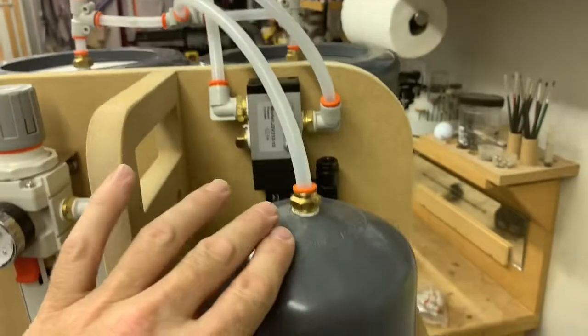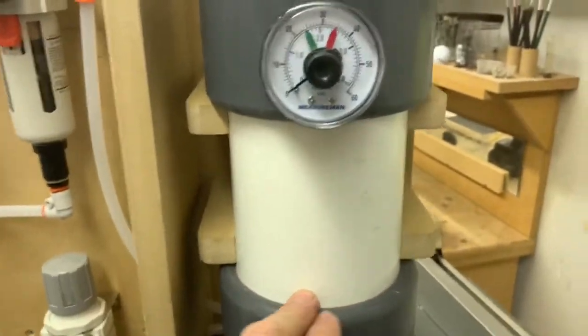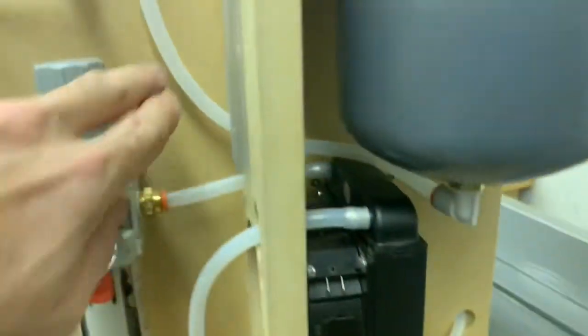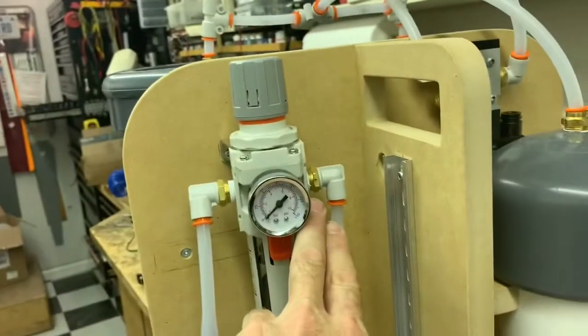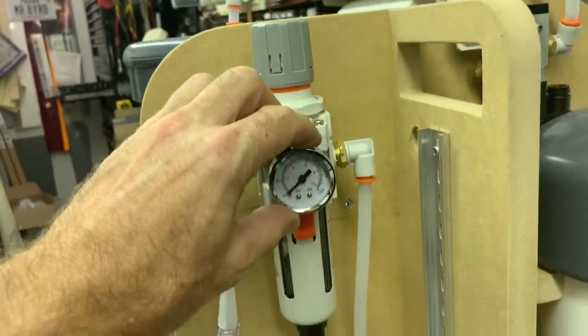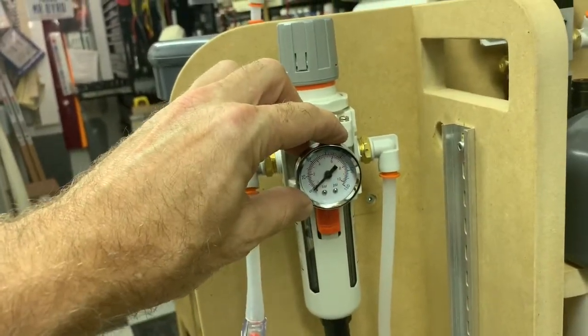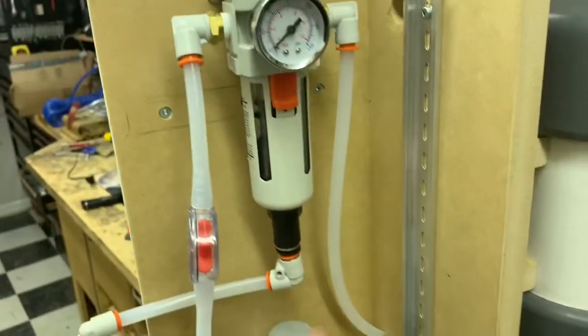Then we come back out to our surge tank which stores the air and then we go out back into a regulator. Again this regulator is a particulate filter as well as a moisture filter and so that will automatically eject any moisture here.